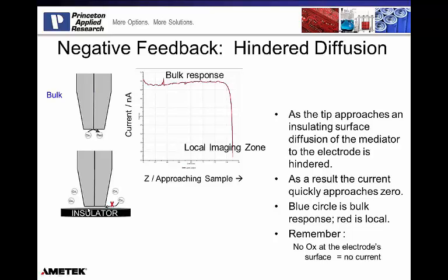Once I get very close to the sample surface, you can almost consider it a thin layer cell, or a small electrochemical cell. It is no longer the entire volume of solution. It has reduced itself to just the volume under, or in contact with, the platinum wire. In the bulk response, we're constantly refreshing the concentration of ox at the platinum wire, so my current is at a high steady-state level. But as I move down close to the sample surface, I've consumed the local concentration of ox, and the bulk concentration of ox no longer has the capability to reach the platinum wire. So you can see why the specific taper and dimensions of the probe are very important.